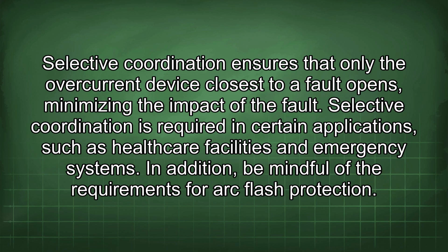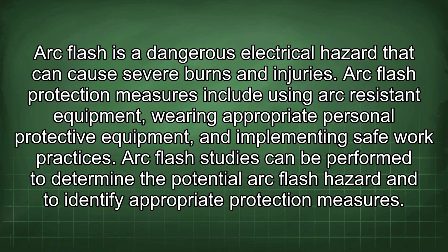In addition, be mindful of the requirements for arc flash protection. Arc flash is a dangerous electrical hazard that can cause severe burns and injuries. Arc flash protection measures include using arc-resistant equipment, wearing appropriate personal protective equipment, and implementing safe work practices. Arc flash studies can be performed to determine the potential arc flash hazard and to identify appropriate protection measures.